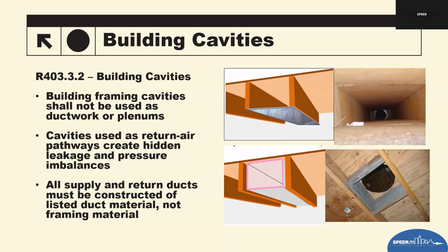So code language states building framing cavities should not be used as ductwork or plenums. That's both return and supply. This is a firm no. So wall cavities, floor cavities, open chases, and rim joist spaces cannot be used to move air, whether supply or return. This eliminates a major source of uncontrolled leakage and thermal bypassing inside of the ducts.